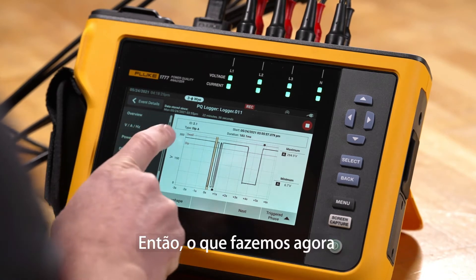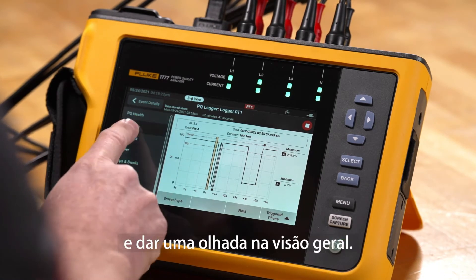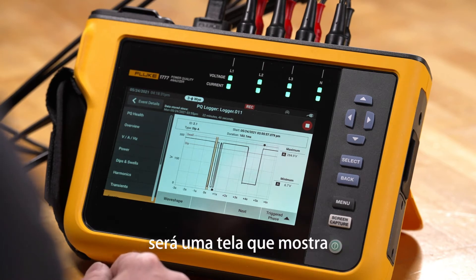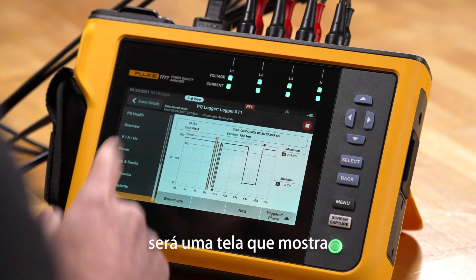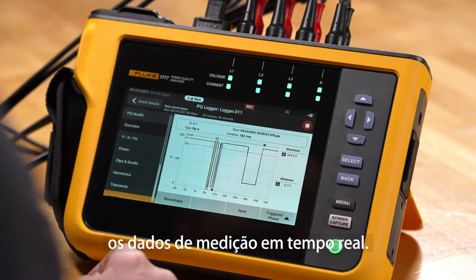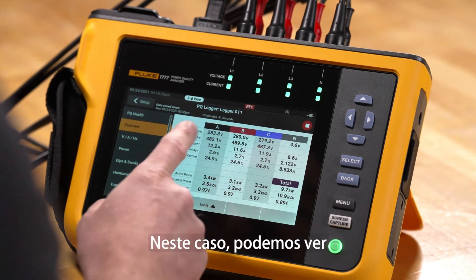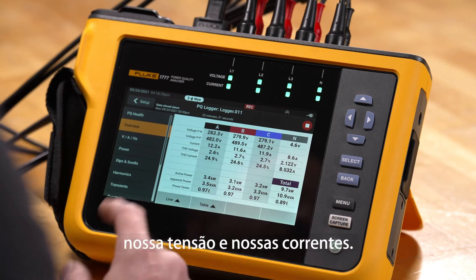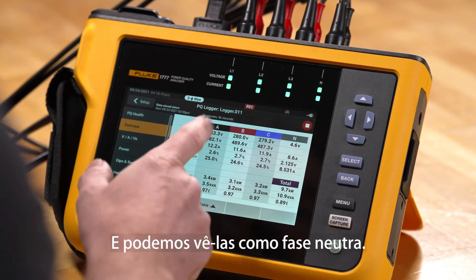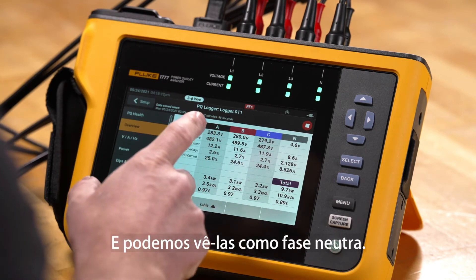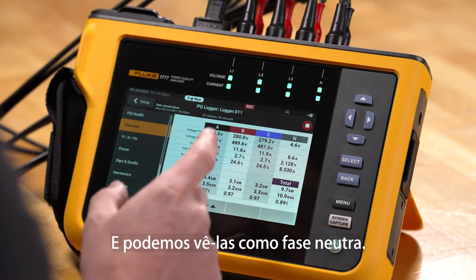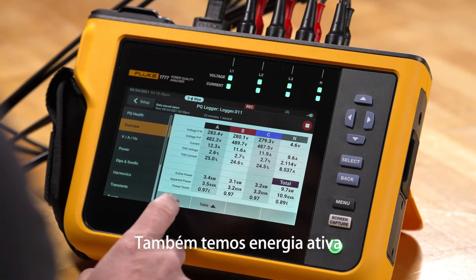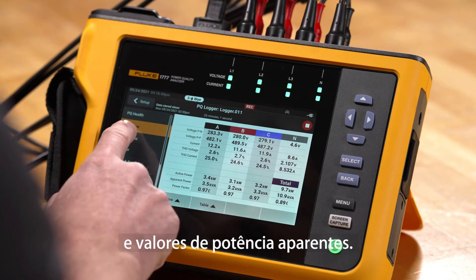We're going to go back up and look at the overview. The overview screen shows us the actual ongoing live measurement data. In a single screen we can view our voltage and our currents — we can see these as phase to phase and as phase to neutral, and we also have active power and apparent power values.